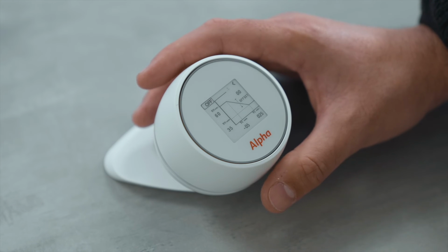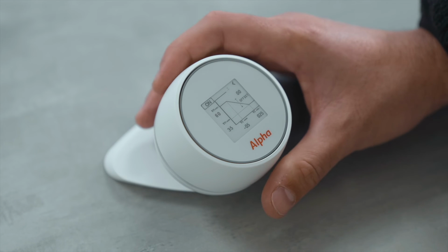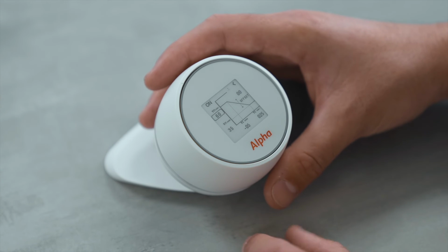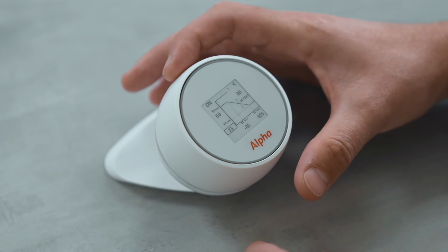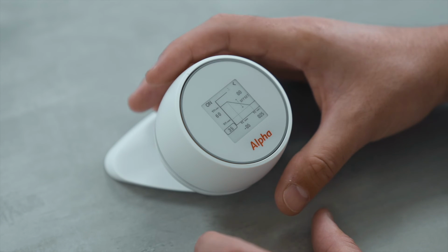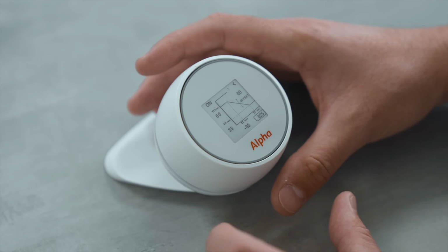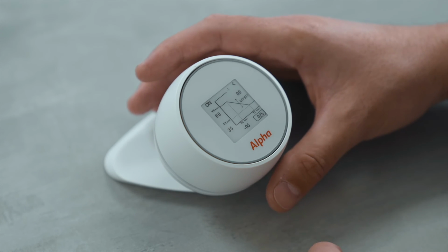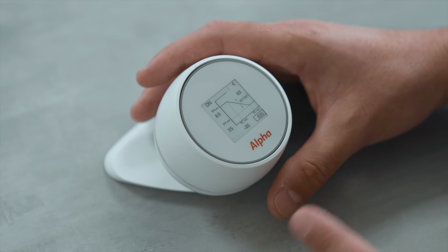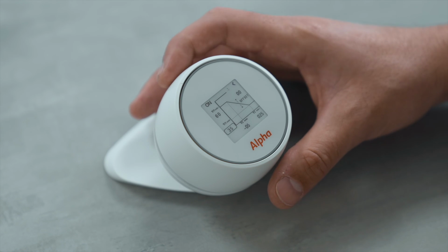So that was thermostat. The next one is curve. So if we go into the curve settings, you can see that we've got the curve off. So we want to turn that on, so the curve is on. The axis on the left simulates our flow temperature. So we've got a minimum flow temperature of 35 and a maximum flow temperature of 60. This is a great setting for radiators. Along the bottom, we've got our operation temperature. So we've got an external temperature of -5 and an external maximum temperature of 25. So in this scenario, if we're looking at -5 or below, we're going to be running at a flow temperature of 60. And vice versa on the graph, that's where we would use our weather comp graph.